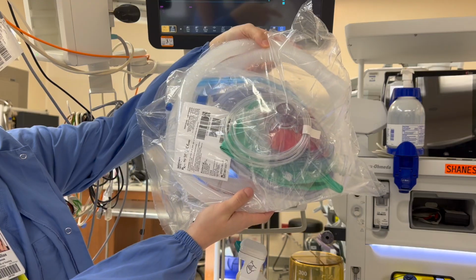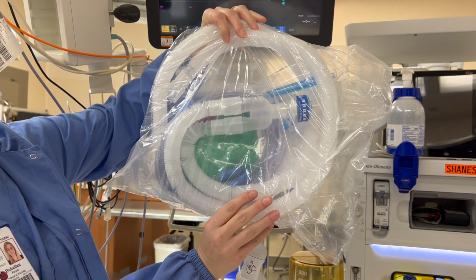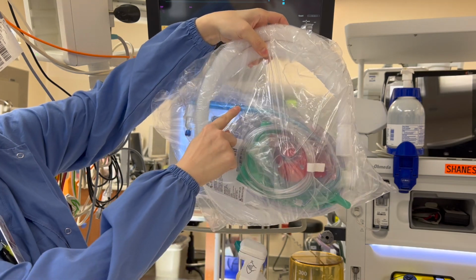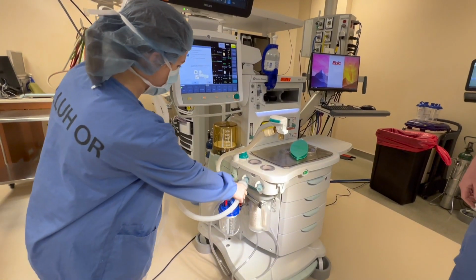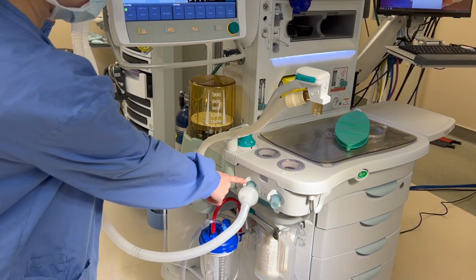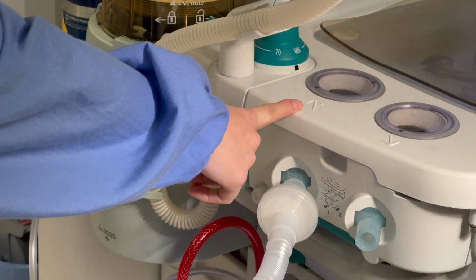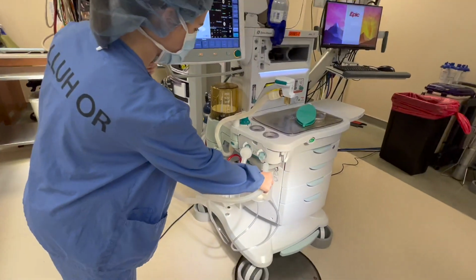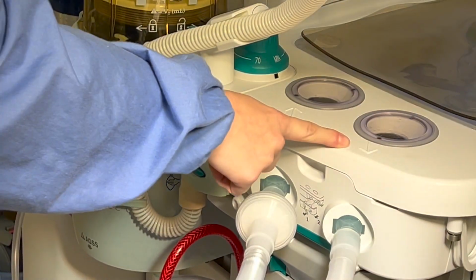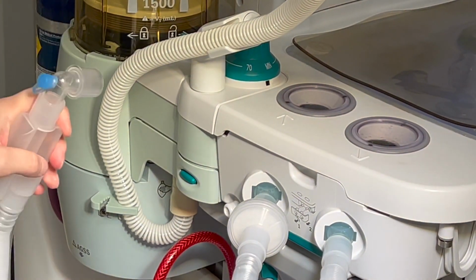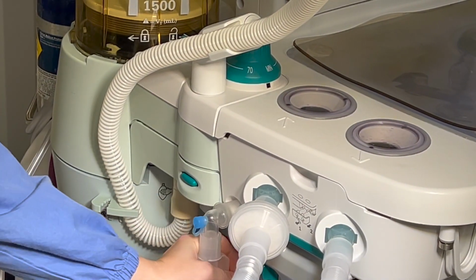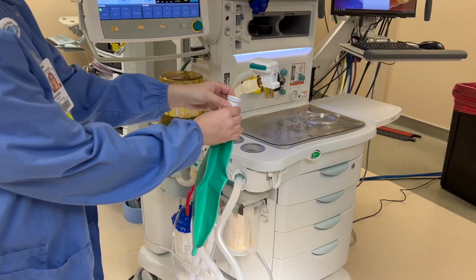This section of the anesthesia checkout is automated and checks for leaks in the machine, circuit leaks, and calibrates the flow and oxygen sensors. Results are reported during each step, so you'll know when errors appear. To start this process, go ahead and find one of these bags, usually in the room, which has your circuit and reservoir bag inside. Go ahead and connect the expiratory limb as shown. It has a picture of an arrow going in to the machine. And then get your inspiratory limb and plug it into the area where there's the arrow going out. Take the patient Y and connect it here as shown, and then get your reservoir bag and connect it.